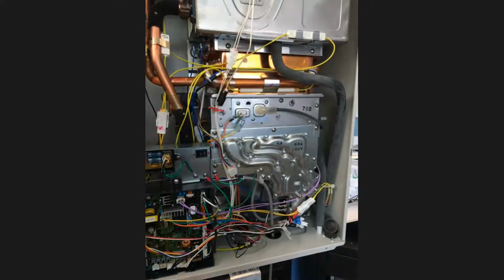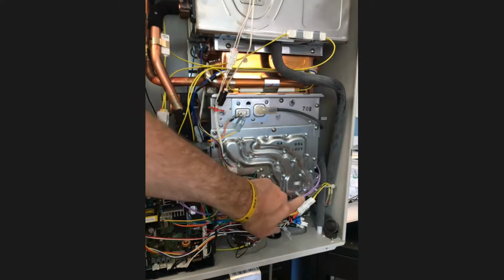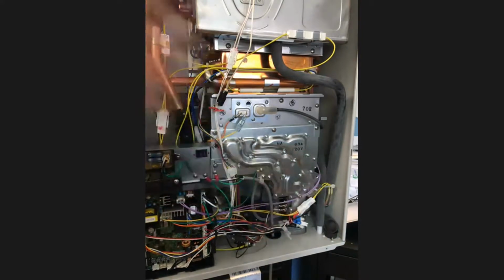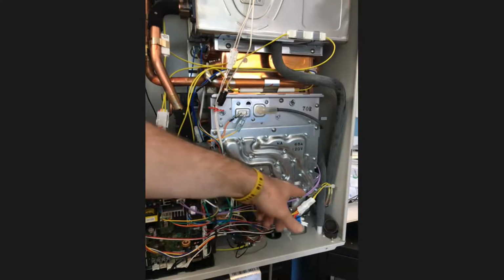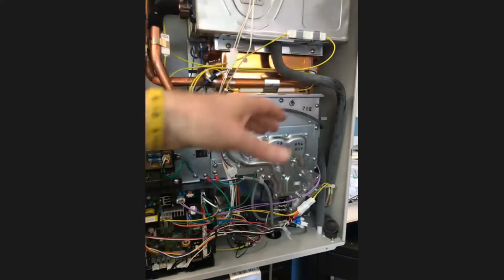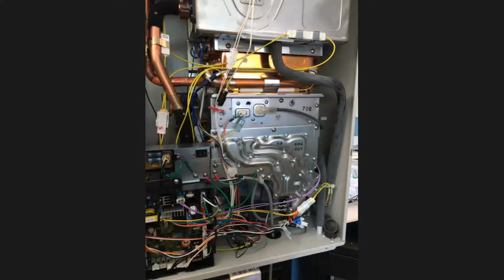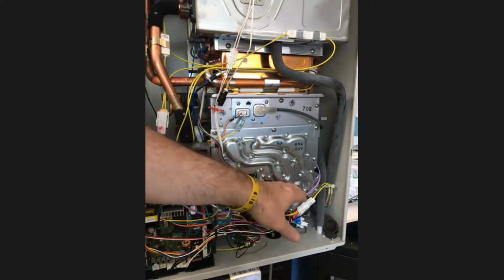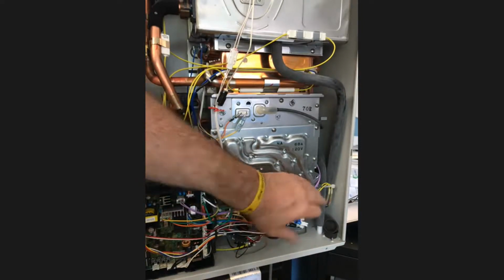A couple of points that may be important for troubleshooting for the technicians here: this port lets me look at pressure within the heat exchanger. Do I have a scenario where I'm over length, maybe an obstruction or whatever? I can take a pressure reading using a manometer right there. So if you're running through tech support issues, that's where we'd go to adjust or at least test.